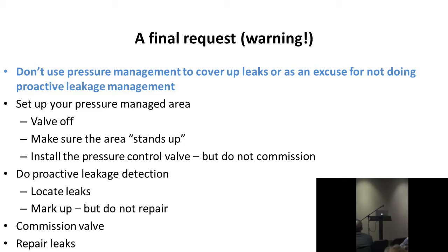So you'll do your design of your pressure management area, valve it off. You then let it run for about a week or so and do what we say, make sure it stands up, which seems a bit of a peculiar phrase, but we do tend to say that, don't we? In other words, I've now valved this off, same process as for the DMAs. Before you put your DMA meter in and put your PRV in, don't commit yourself to that expenditure. Make sure that that DMA will maintain supplies during your peak demand periods. If it doesn't, you've got to redesign it a little bit. Perhaps reduce the size of the area or what have you, change the valving.